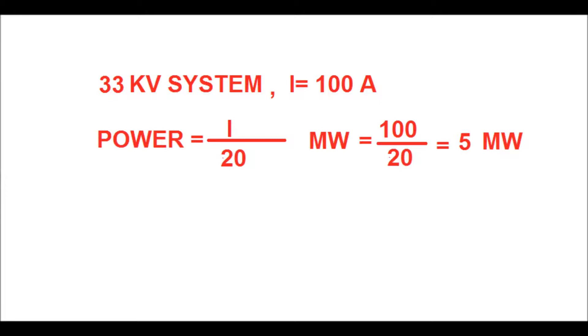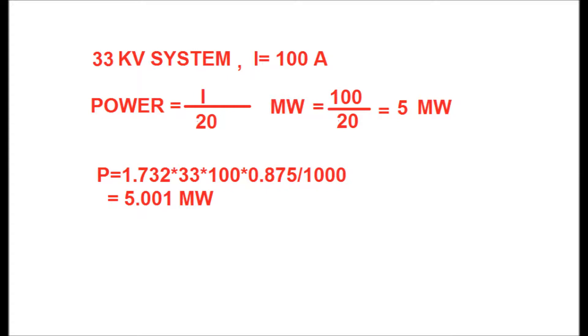The equation is P = √3 × V × I × cos φ, with power factor taken as 0.875: P = 1.732 × 33 × 100 × 0.875 divided by 1000, giving 5.001 megawatts. So by thumb rule, for a 33 kV system, just divide the current by a factor of 20 to get the power in megawatts.